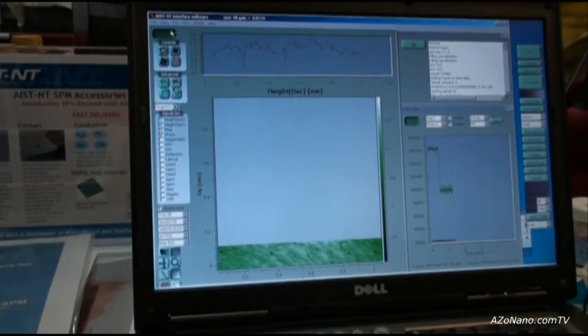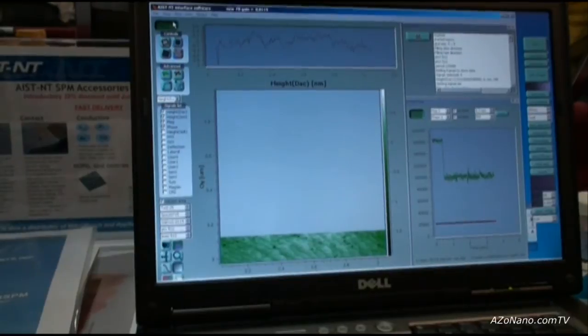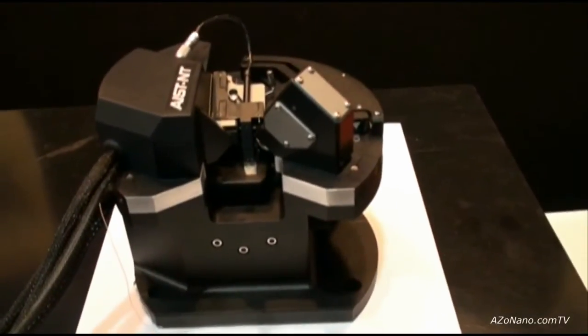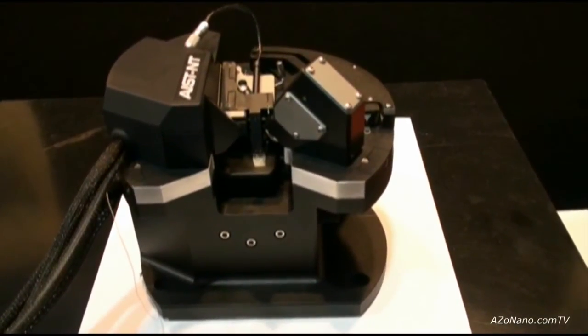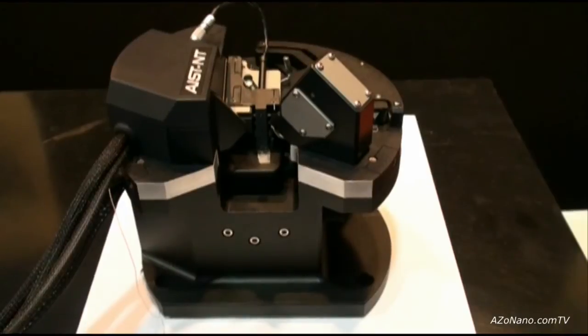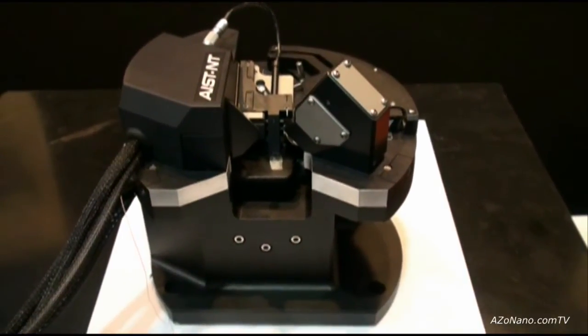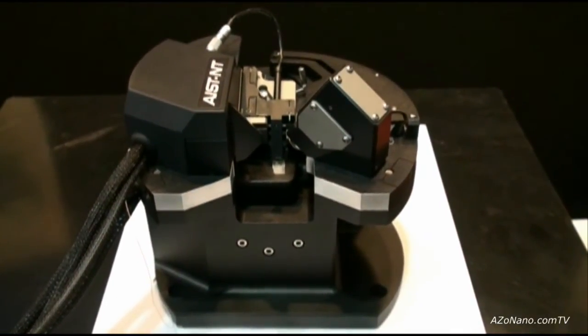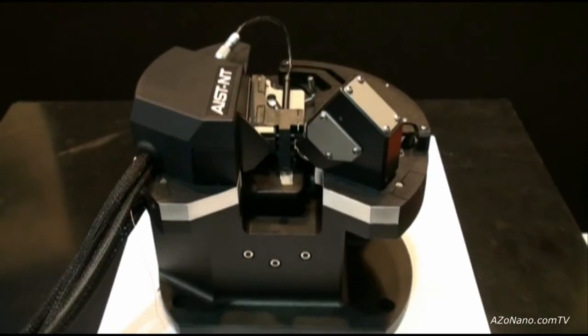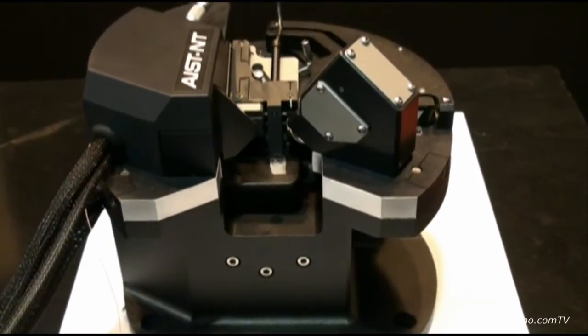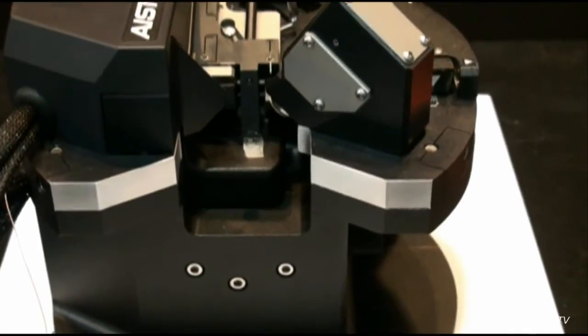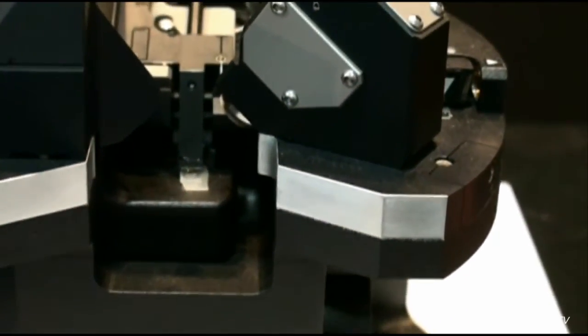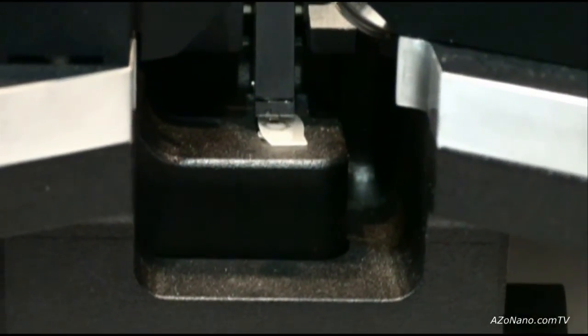The instrument itself is built to work as an AFM and can be integrated and built up to do atomic force microscopy with Raman. As you can see, the system is designed to add in the optics for Raman measurement. You can do horizontal optics and vertical optics. The system is built to do that. You can do transmission Raman or reflection. It can also be mounted on an inverted microscope, so if you want to do SNOM or fluorescence, you can do that also with that basic system.